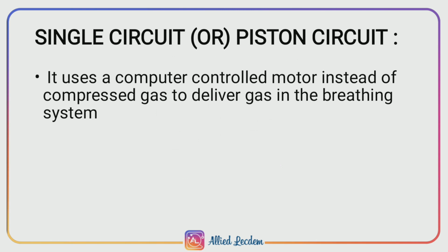Single circuit or piston circuit. Piston ventilators do not require driving gas. They are driven by an electric motor to move a piston, thus compressing the gas and moving it into the patient's lung.